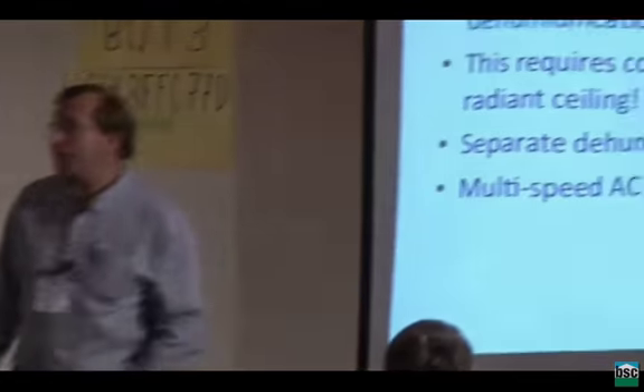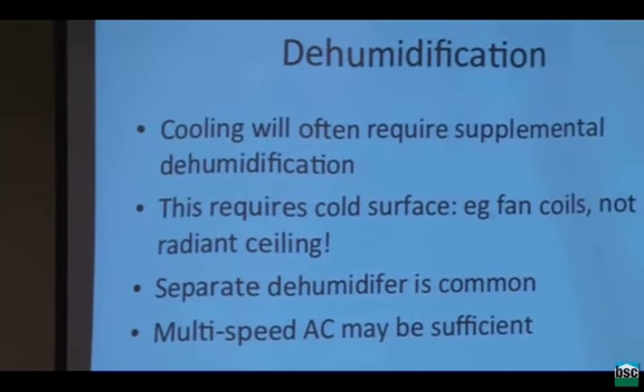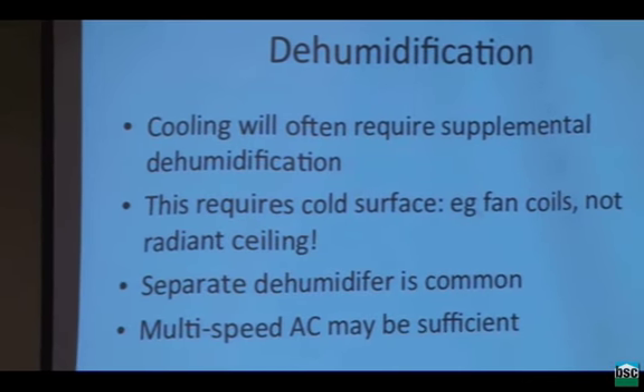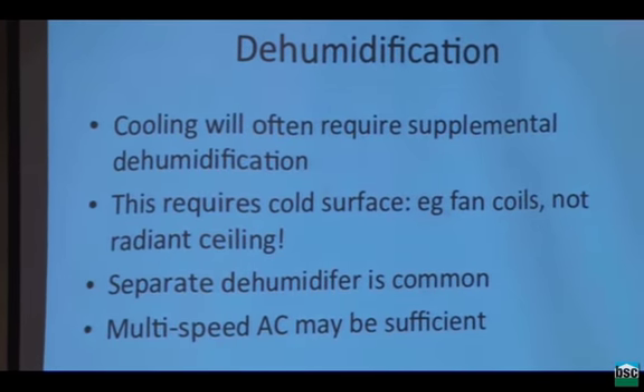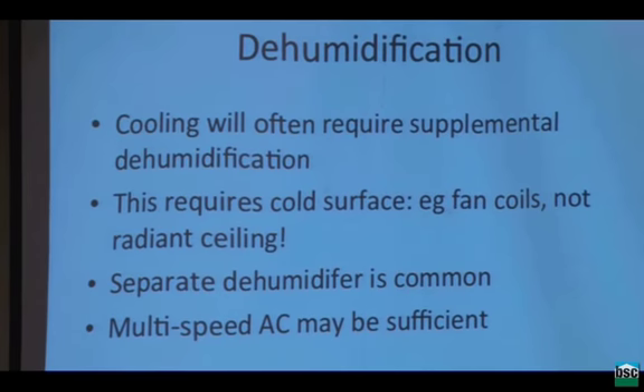Okay, just before a break, the dehumidification, as I've mentioned several times, cooling only will require supplemental dehumidification, and this requires a cold surface, like fan coils. The problem with radiant floors is that radiantly cooled floors, right? You could cool a ceiling or cool the floor, but you can't cool it below the dew point temperature of the air in the building. And it does zero dehumidification. You want it to do zero dehumidification.